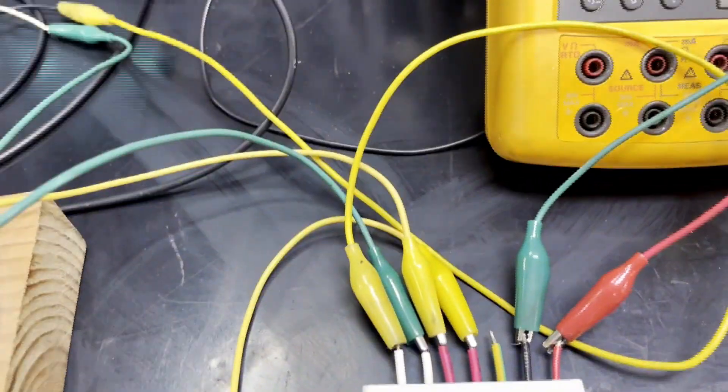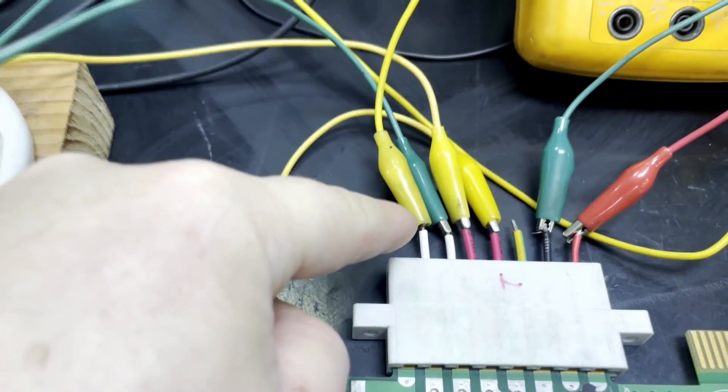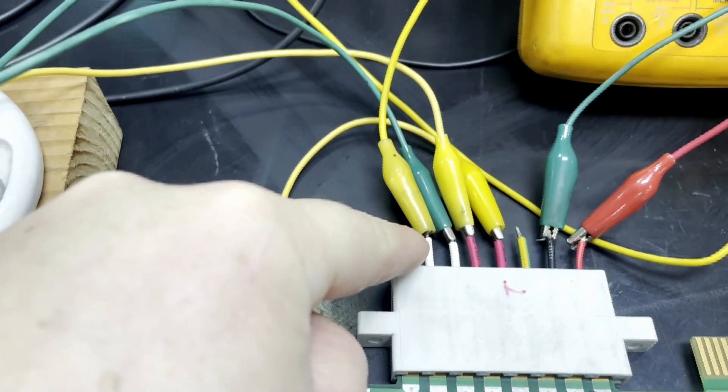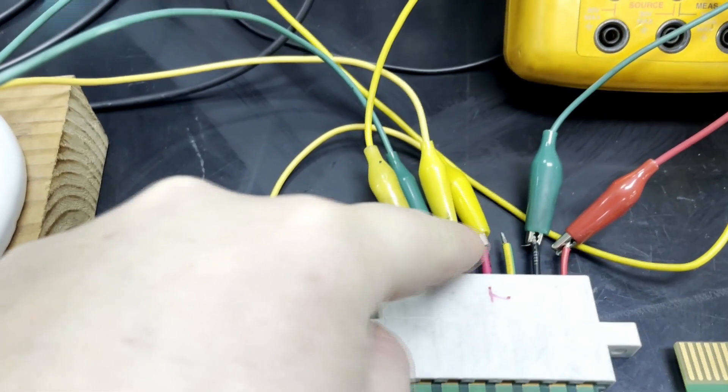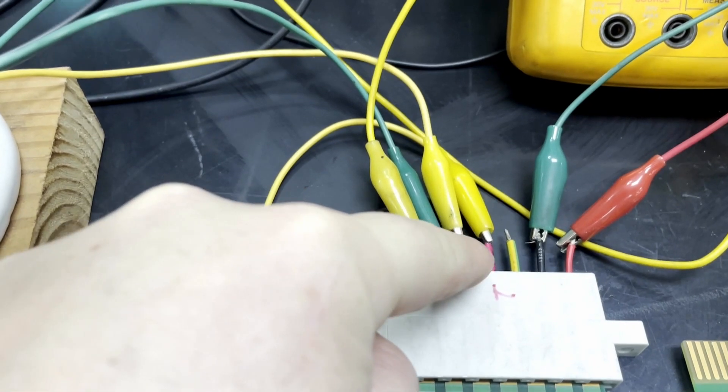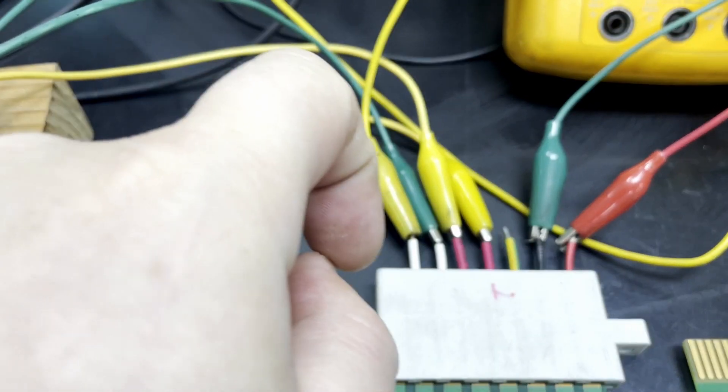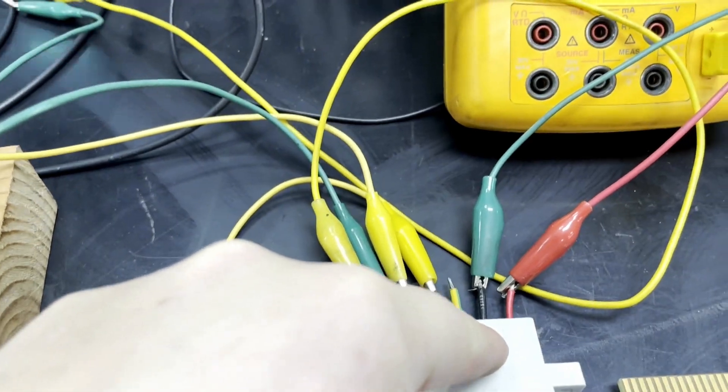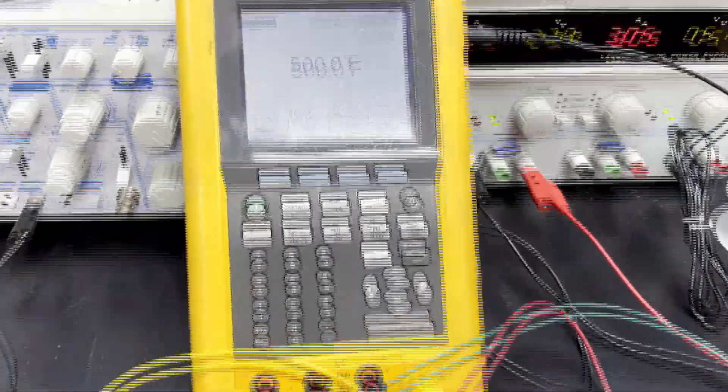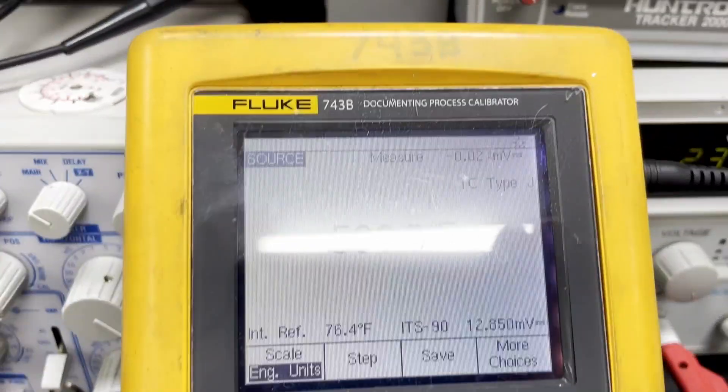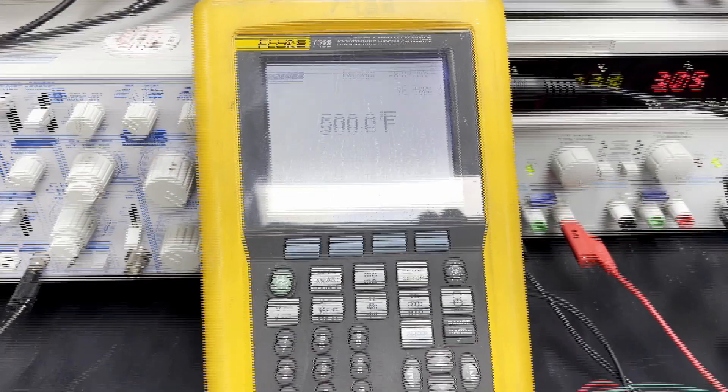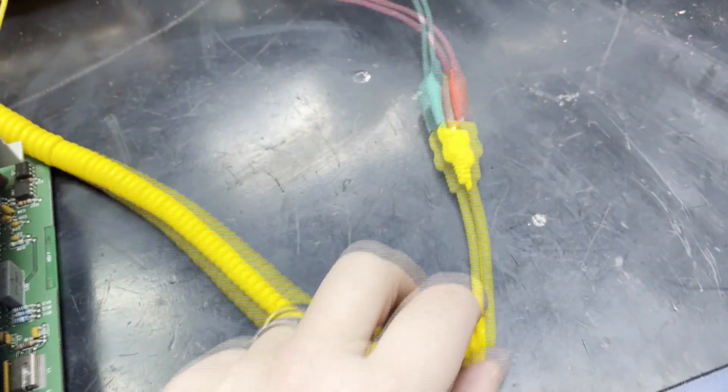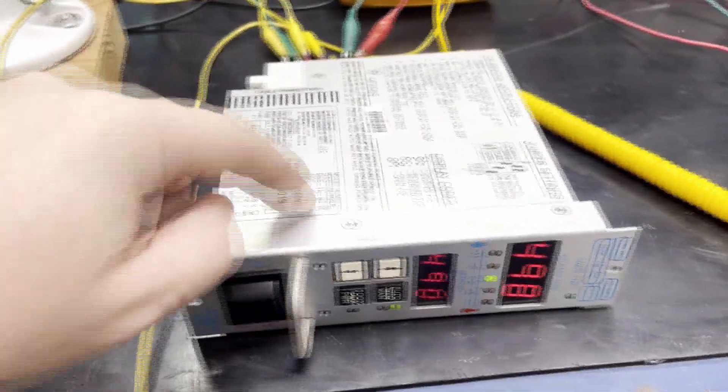So here we have our connection set up, which is we have our 220 AC coming in here. We have our lamp set up on the output of these two plugs here, and then we have our positive and negative inputs to our simulator, which is the Fluke 743B Documenting Process Calibrator, which will provide a simulation of a J-type thermocouple that would normally be plugged into this device to give us a temperature reading in the system.